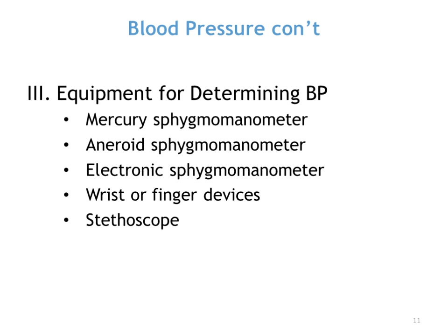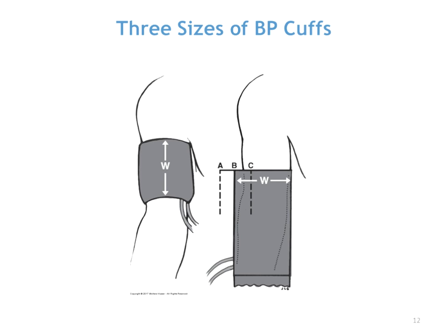So what's the procedure? You're going to prepare the patient. All right, this is telling you the sizes of the cuff, and the nice thing with the cuffs that we have at the MEC, we have a standard adult. It tells you where to put these hoses, as well as when you're wrapping the cuff around the patient, it tells you when you need a larger cuff. So it's got those markings on it, just as a guide.